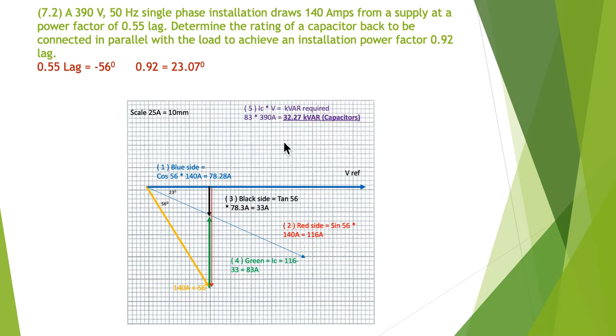Step five: the current times the voltage tells me the kVAR required. My 83 amps multiplied by 390 volts equals 32.27 kVAR. So 32.27 kVAR of capacitors will produce 83 amps of current at 90 degrees, which will drag that up and reduce my angle from 56 to 23 degrees.